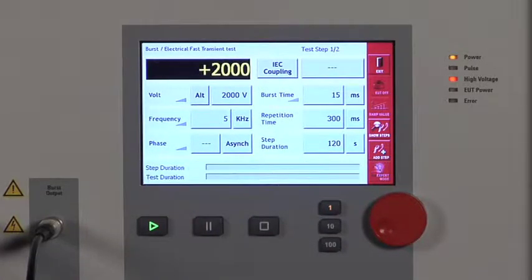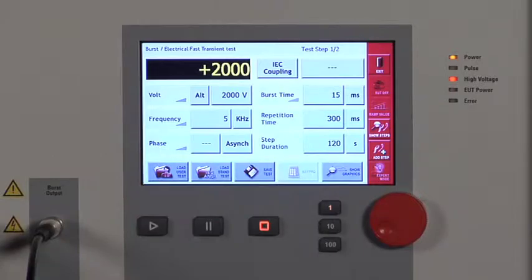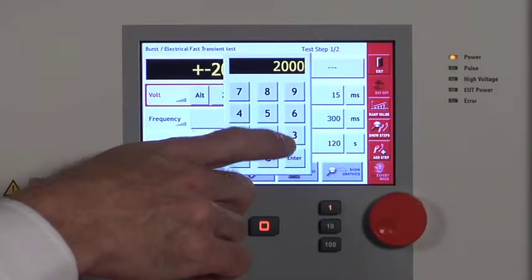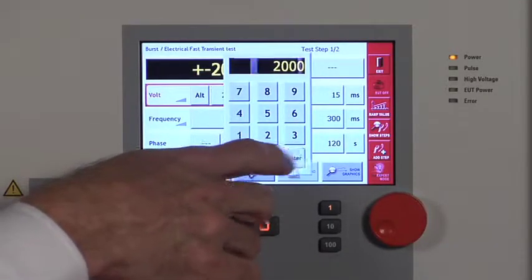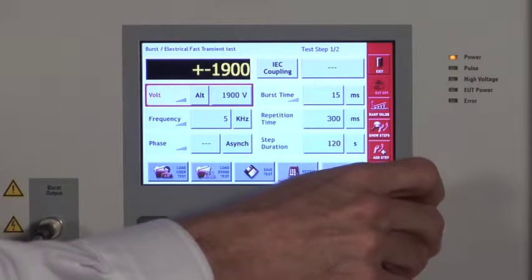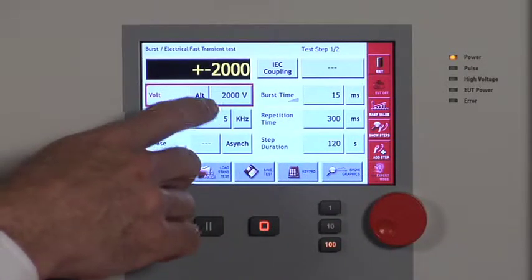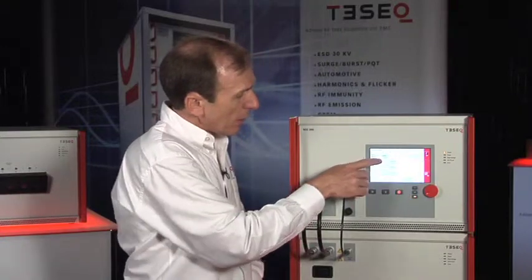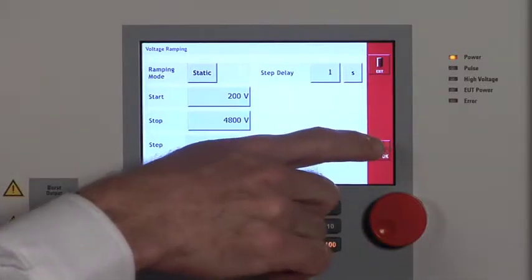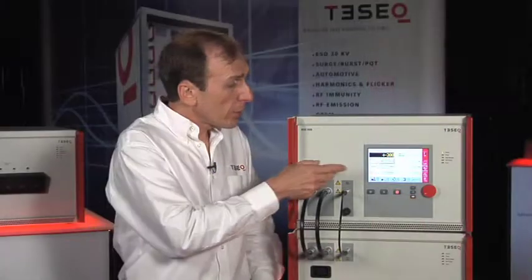It now can be automated by this software interface. We're going to begin. The test can be stopped with the stop key. For changing settings like voltage, it's quick and easy. I can call up a keypad and enter a precise number. I can also use the spin dial control to quickly raise and lower the test level, change polarity — plus, minus, alternating. I can create a ramping test that starts at a low level and increases to a high level by a specific test step size. So you can see the touchscreen interface makes it very quick and easy to control the system and make the settings required for your test.